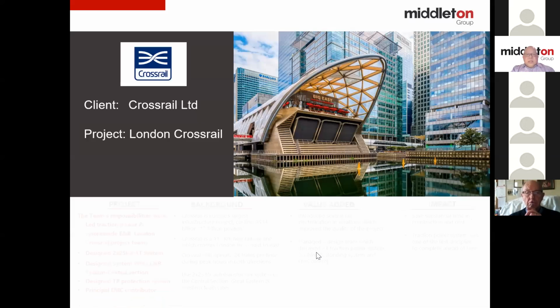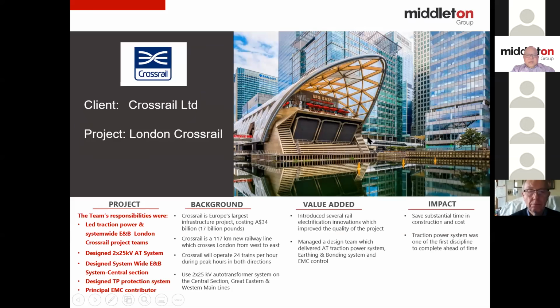So that's that one. And this is my latest one. Before I came to Australia, I lived in the UK for 31 years, predominantly in London. And this traction power system, I was the reference designer for this system. The price has gone up to $17 billion. Some said might be 18, and $34 billion Australian. I was the lead traction power engineer and also the system-wide earthing and bonding for the central section of the Crossrail project. And I came up with the idea of 2 times 25 kV AC. My client's engineer said, "You're mad, that 2 times 25 kV AC for the metro system, that's normally used for high-speed train." I said, "Well, we have a high-capacity railway using a booster or rail return, and we need to have 2 feeder stations feeding into the tunnel with neutral section."